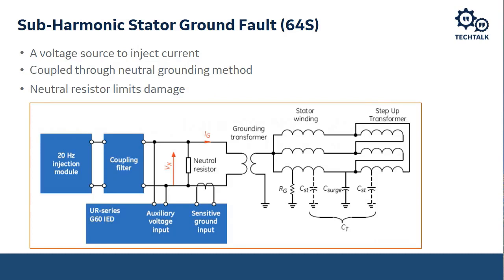The last method we're going to talk about is the subharmonic stator ground fault, or the injection method. Basically, we couple an injection set to the grounding transformer, which is coupled to the neutral of the generator. We inject a low frequency, subharmonic signal into the generator and measure the resulting current. If the generator is not faulted, it just has the stray capacitance and surge capacitance, so the currents we're going to see are reactive only, or capacitive reactive currents. Whereas if we do have a ground fault within the generator, we'll see a high level of resistive fault current. So that's what this set is doing. It injects the voltage, we read the resulting current with our relay, and the relay extracts the resistive component of that current. If that resistive component is pretty high, then it's going to trip and say there's a ground fault.